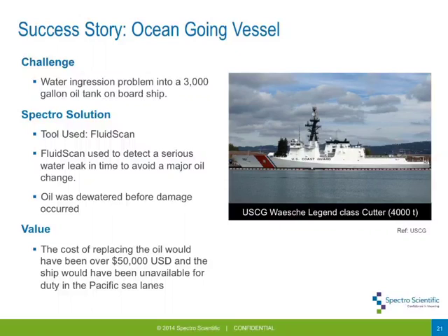Let's go through some success stories. An example of just catching water was with the Coast Guard. They had a water ingression problem with a 3,000-gallon oil tank on board their ship. They suspected water, used a portable FluidScan tool, detected the water right then and there, and before the ship left port they solved the problem, fixed the water leak, and avoided a major oil change — the oil was de-watered before things got out of control. If they had waited for the oil analysis report, they would have been out to sea and had to call off the mission. They estimated it would have cost them $50,000 — and in one single incident, they justified their entire program.